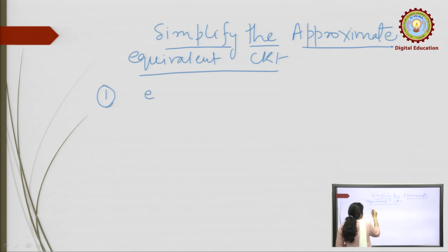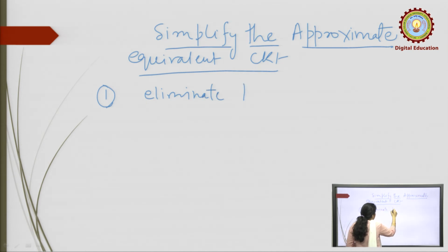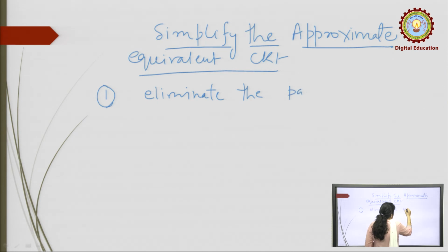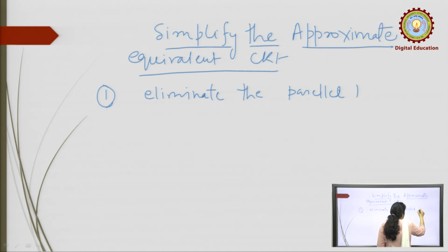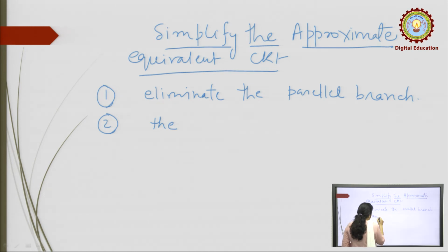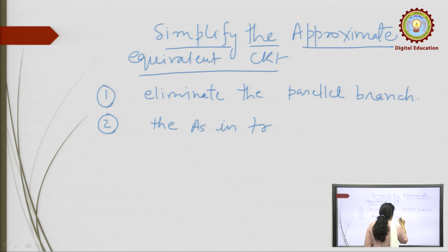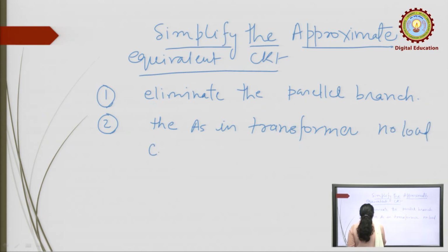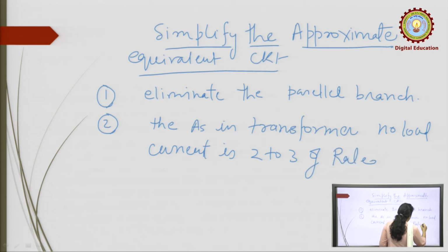How do you simplify this? You eliminate the parallel branch, because for a high rating of transformer, suppose 500 kVA and 1000 kVA transformer, the no load current is 2 to 3% of the rated current.